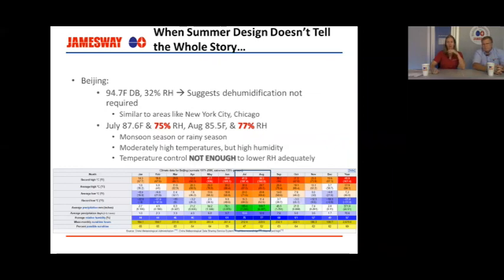So then if we go, and these charts here are available on Wikipedia for most major and a lot of minor cities around the world, you'll see in the middle here, July and August, our average high temperature is looking at like 87, 85 degrees Fahrenheit, but our relative humidity numbers down here in the blue band are sitting at 75, 77%. And this is a monsoon season, a rainy season. And the problem here is that the temperature isn't super high, so our AC unit isn't running constantly, but our humidity is high. So the AC unit on its own is not enough to lower the relative humidity during this situation. So they need dehumidification because of that. So, rule of thumb, start right there. If you have monsoon or a rainy season, you require dehumidification for that season.